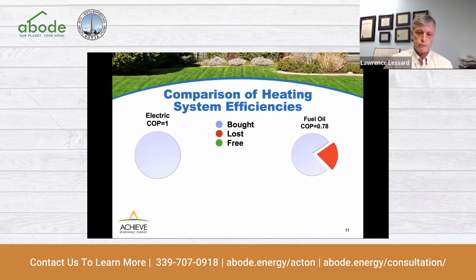In a fossil fuel system, that's never the case. You always have some of the heat going up the flue. Here we have a pie chart showing what you buy and what you lose with a 78% efficient, so maybe like 1970s, early 1980s fuel oil furnace, where you've got almost 30% of the heat going up the flue. So you pay for the whole pie, but you only get to use 78% of it.